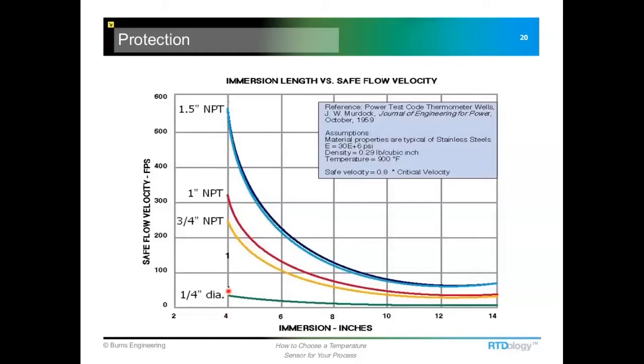The probe can start to shift. The sensing element could actually go open circuit. And if it stays in there long enough, the probe could actually break off and go downstream and end up in, it's never a good place. Now, when we add a thermal well at that same 4-inch immersion, and this is one that's got a 3/4 NPT process connection on it, so the stem would start out at a 7/8 inch diameter, and they typically taper down to about 5/8. So that bumps up the safe flow velocity to about 250 feet per second. So it makes quite a bit of difference, and then going up in size increases it even more.